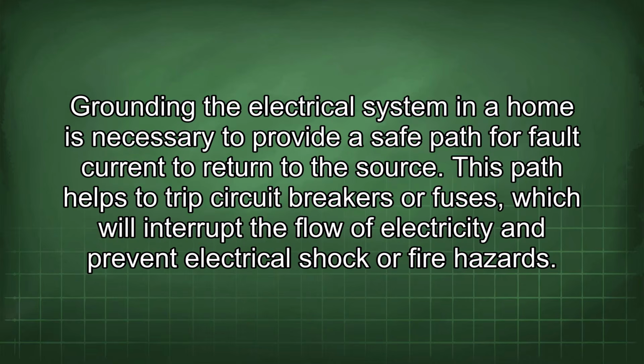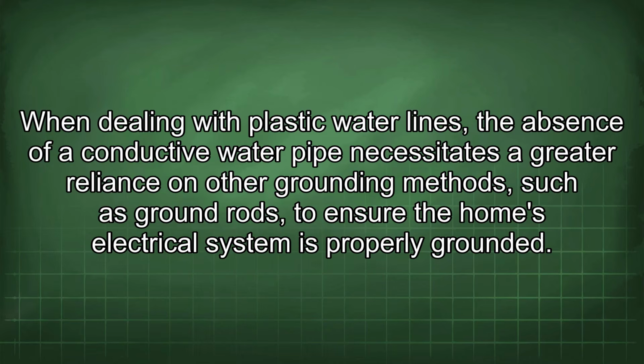area. Grounding the electrical system in a home is necessary to provide a safe path for fault current to return to the source. This path helps to trip circuit breakers or fuses, which will interrupt the flow of electricity and prevent electrical shock or fire hazards. When dealing with plastic water lines, the absence of a conductive water pipe necessitates a greater reliance on other grounding methods, such as ground rods, to ensure the home's electrical system is properly grounded.